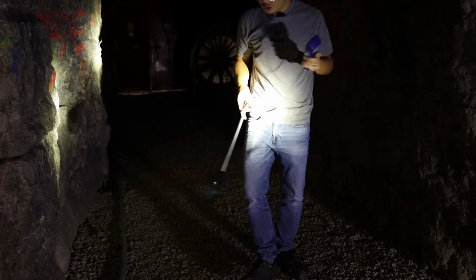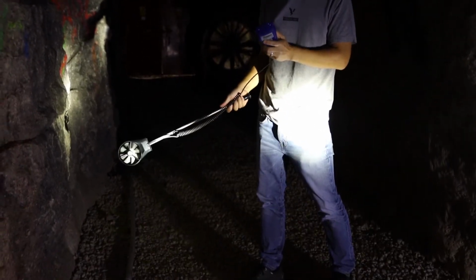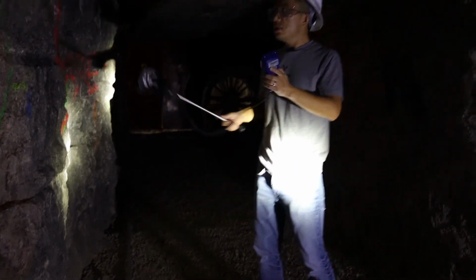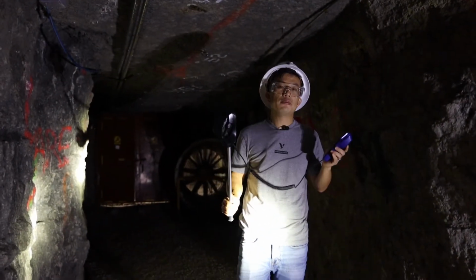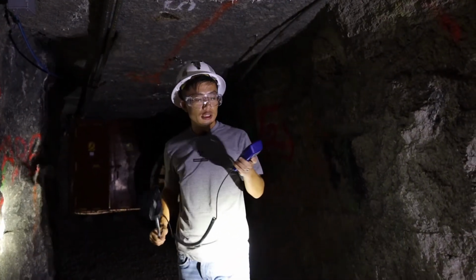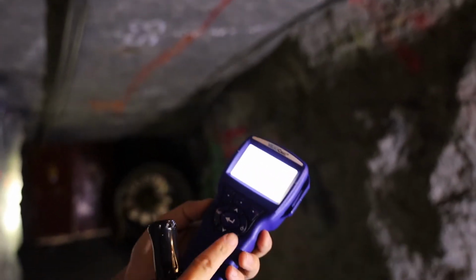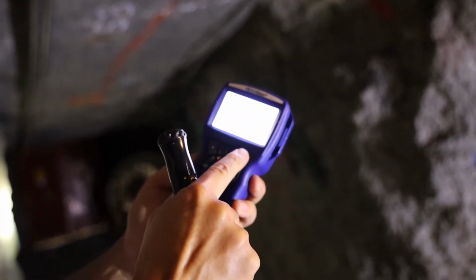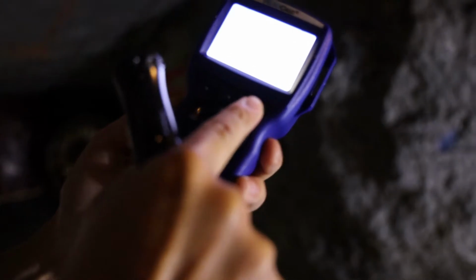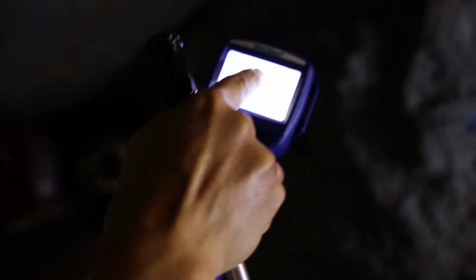Also, you need to make sure you're not moving this so fast. The speed has to be less than 0.2 meter per second, and the entire time of finishing the traverse has to be more than 1 minute. To look for the average velocity, we just go to stats, and the current measurement is 58. The average is 0.76 meter per second.